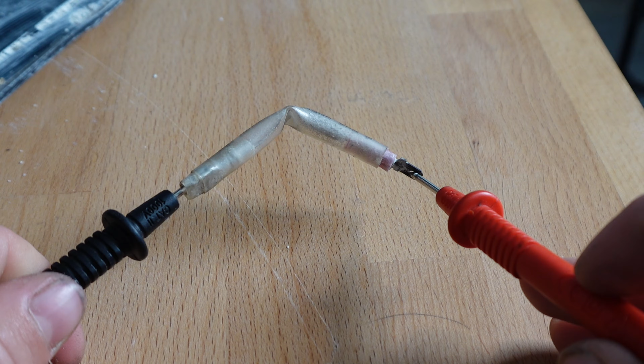Set your meter to continuity and put one probe on each side of the thermal cutoff. If you have continuity, then the thermal cutoff is good. If you do not have continuity, then your thermal cutoff is bad. Switch that bad boy out. You should be good to go.